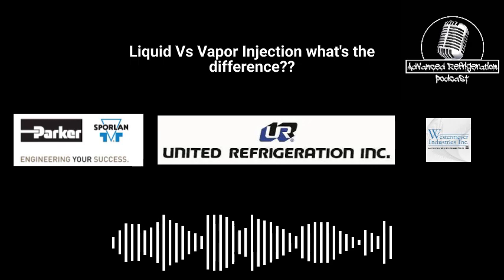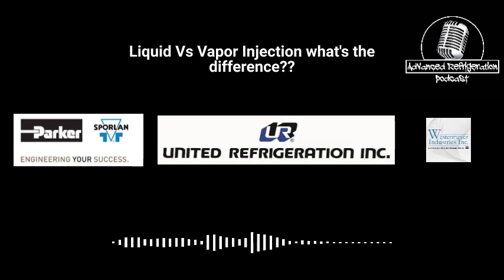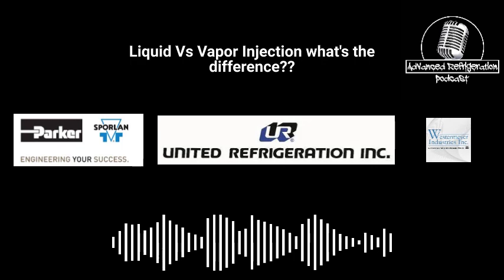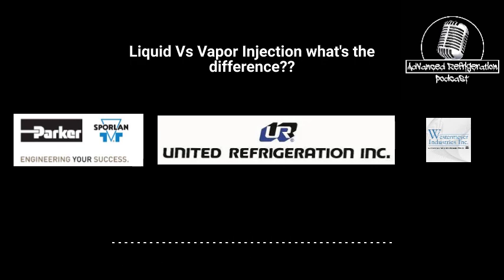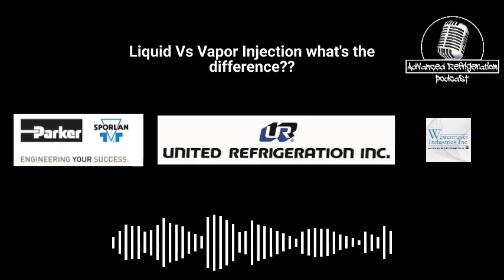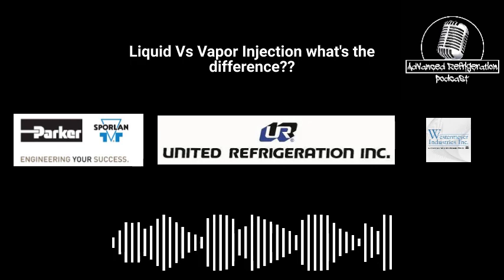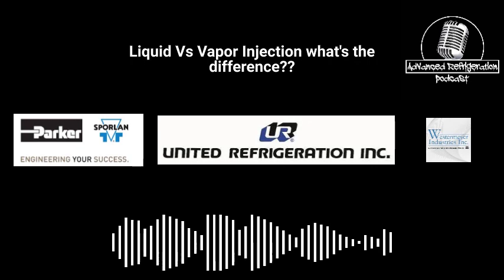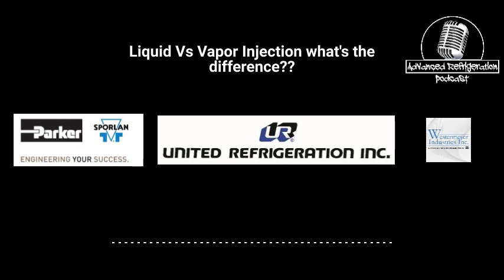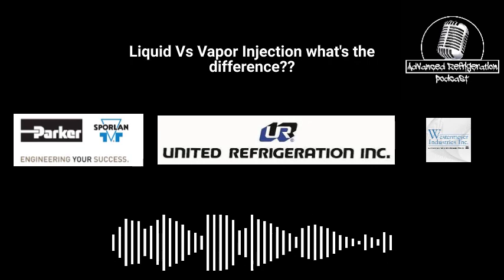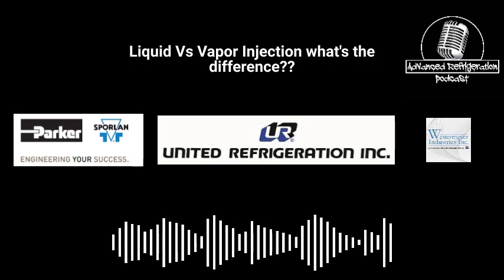The reason I use the lower liquid injection temperatures is because a lot of these ones that are like the 230, that compressor could be running 210 degrees. It's hot. It's overheating oil. So injecting liquid at 190 degrees, you're not using that much more capacity to do it. But at the same time, that compressor's running cooler and you're keeping it out of that danger zone. Every manufacturer has a danger zone. I don't like seeing compressors over 210 degrees at 6 inches from the compressor. That's usually when you start getting to that danger zone. When you get to 230, you're breaking down oil.